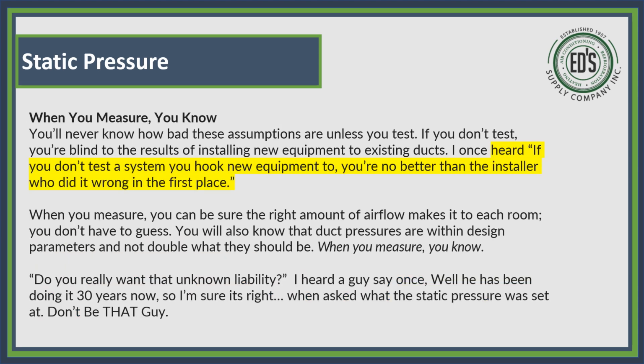When you measure, you know. You'll never know how bad these assumptions are unless you test. If you don't test, you're blind to the results of installing new equipment to existing ducts. I once heard, if you don't test a system you hook new equipment to, well, you're no better than the installer who did it wrong in the first place. Keep that in mind. That is so true.